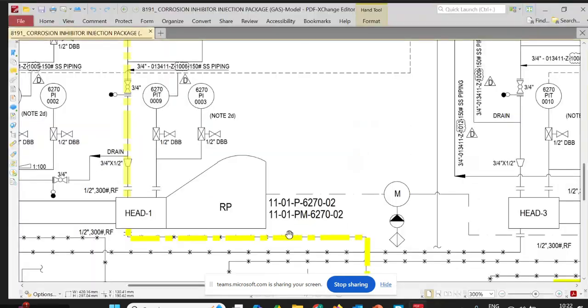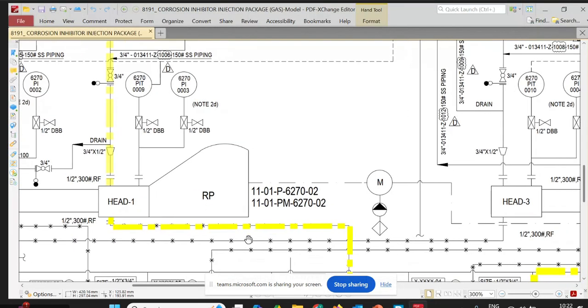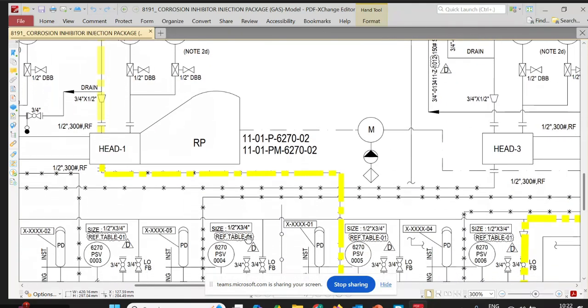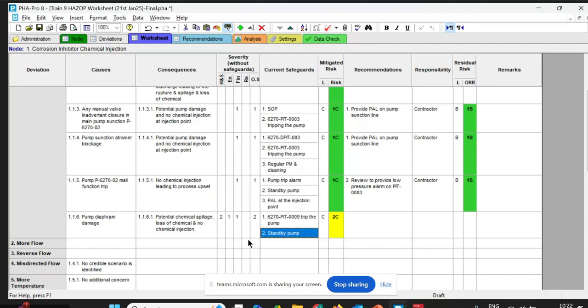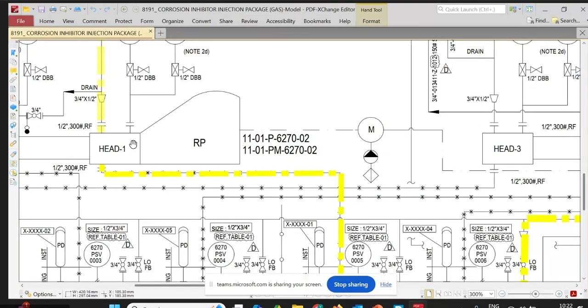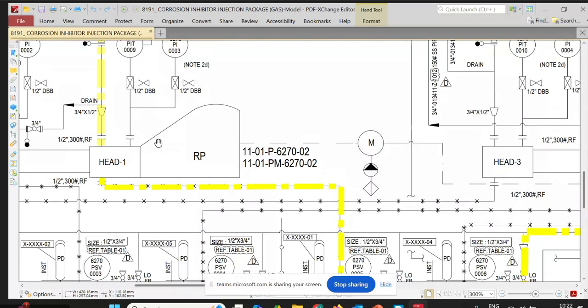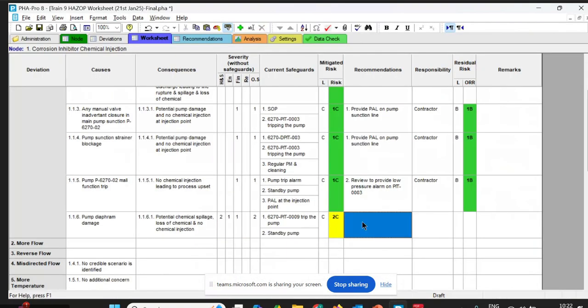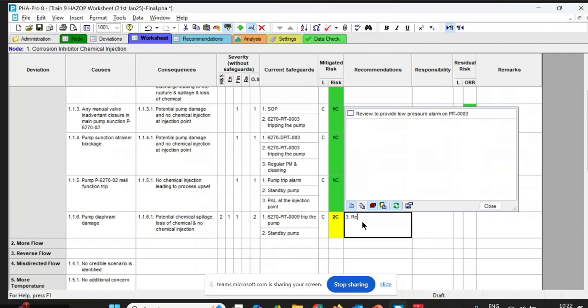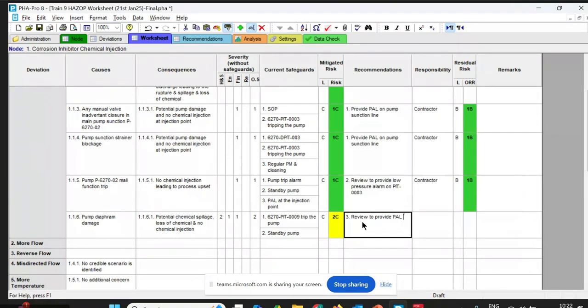Very good. We already addressed this comment with the contractor vendor and they already agreed to provide it, but until now it is not reflected in the P&IDs to have a dedicated transmitter for each pre-alarm. But you need a dedicated one, Khalid. This is not required. It is general. I agree with you, it's not a critical service, but as a general philosophy applied for the project, we have to trigger a pre-alarm before going directly to the trip. Okay, I would say review to provide PAL on a separate PT.